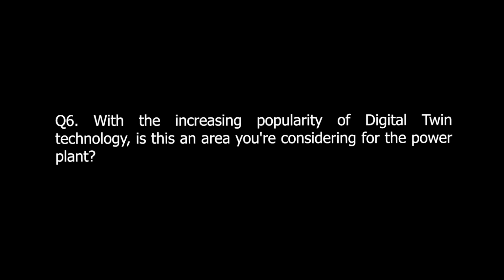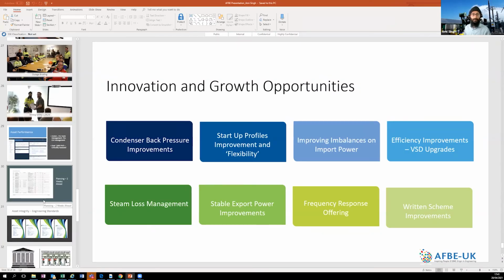No, that's an area for a lot of development for us at the moment. In all honesty, that's something we haven't really embarked on. What we have done is get over 5,300 analog points. For every piece of machinery, any analog point that varies in real time, we have artificial algorithms in place for those 5,300 analog points, using a smart algorithm - it's the GE proprietary product we use in thermal called GE Smart Signal - that looks at the actual analog value versus what the model predicts it should be, and then drives an alarm on that. That's been quite successful for us as a business.